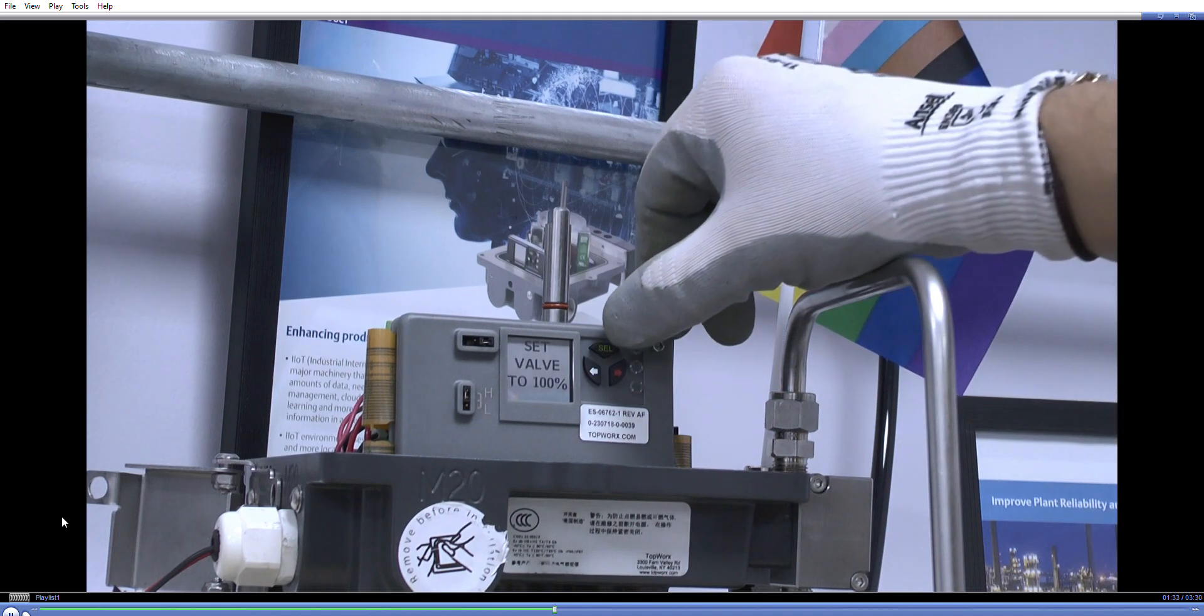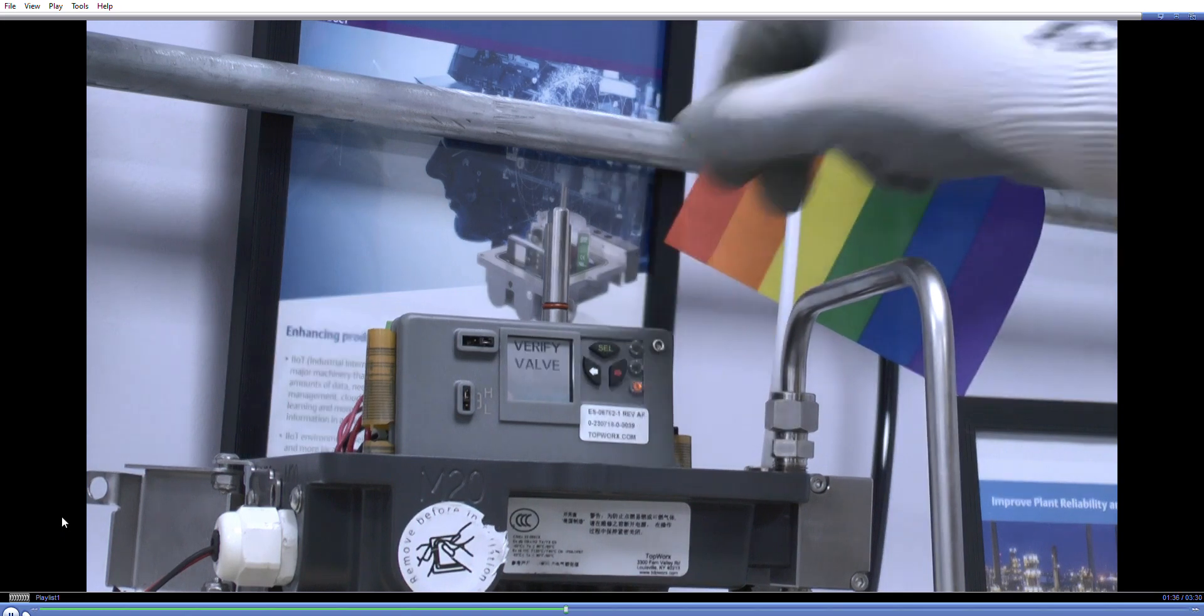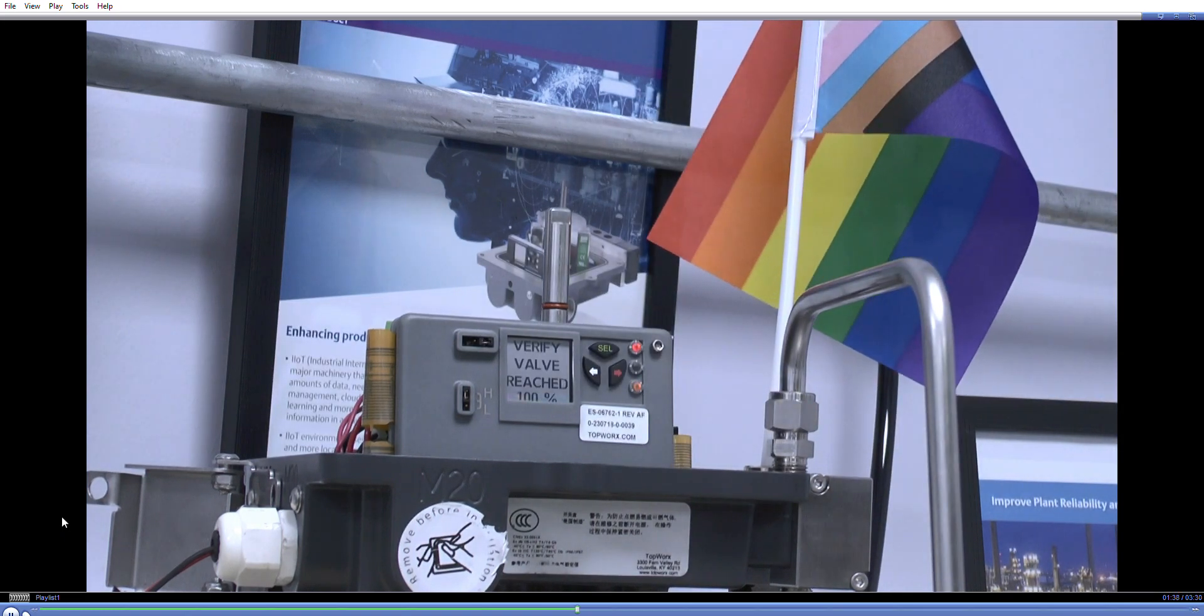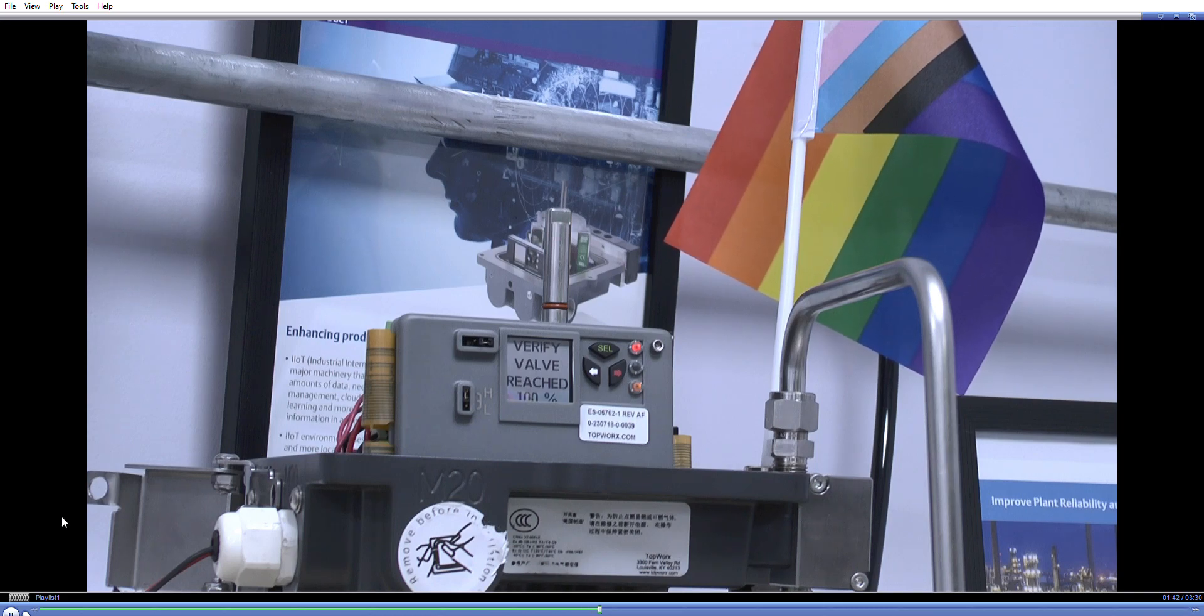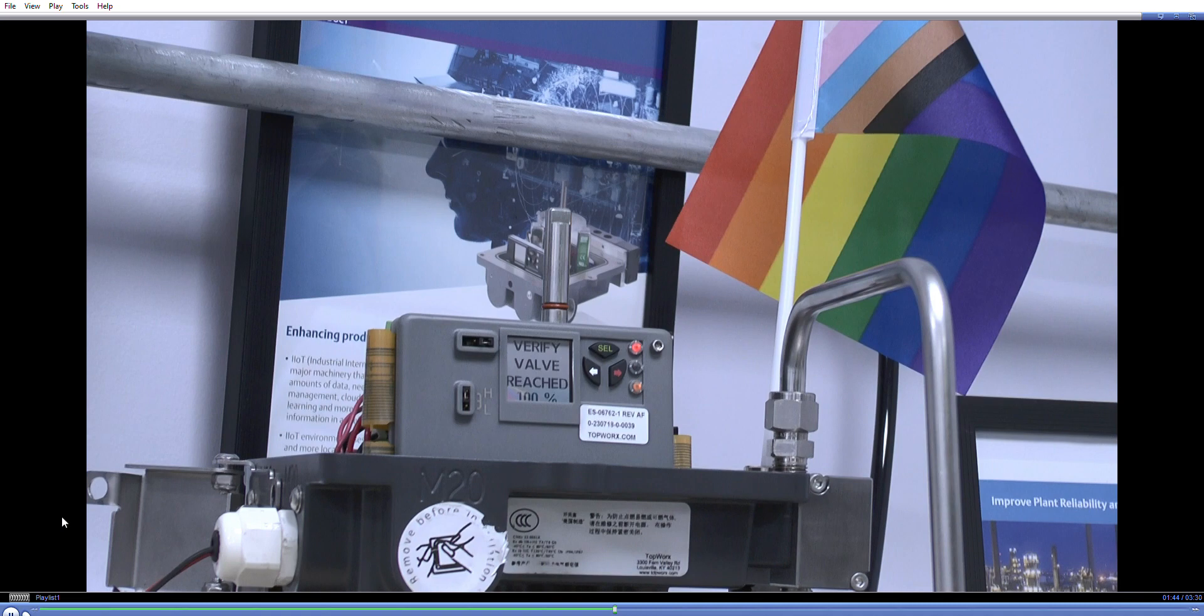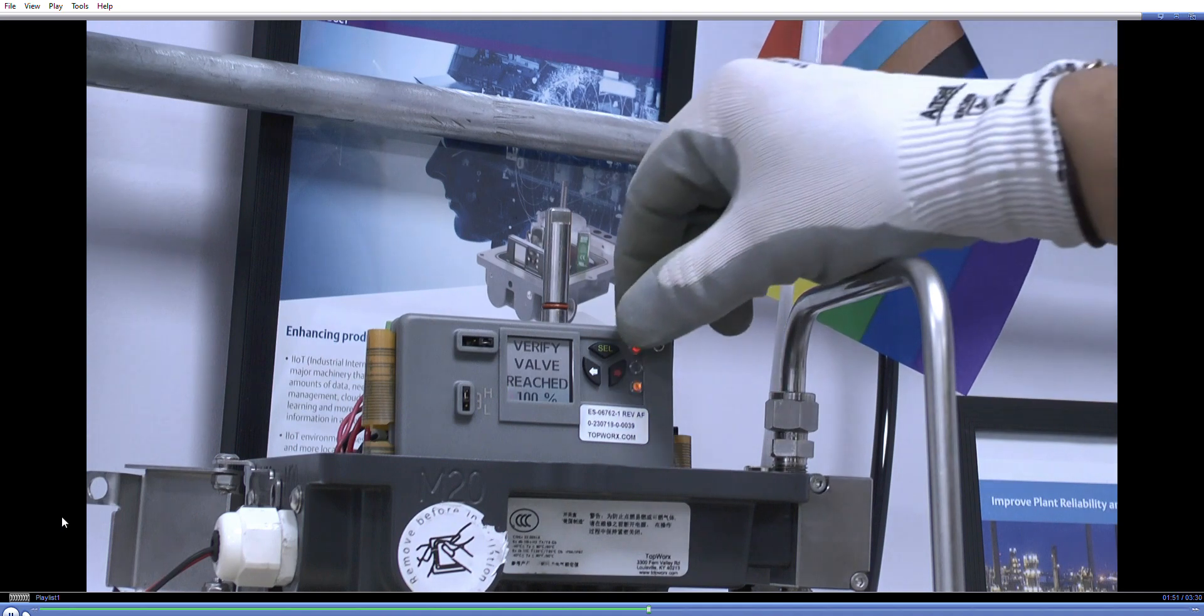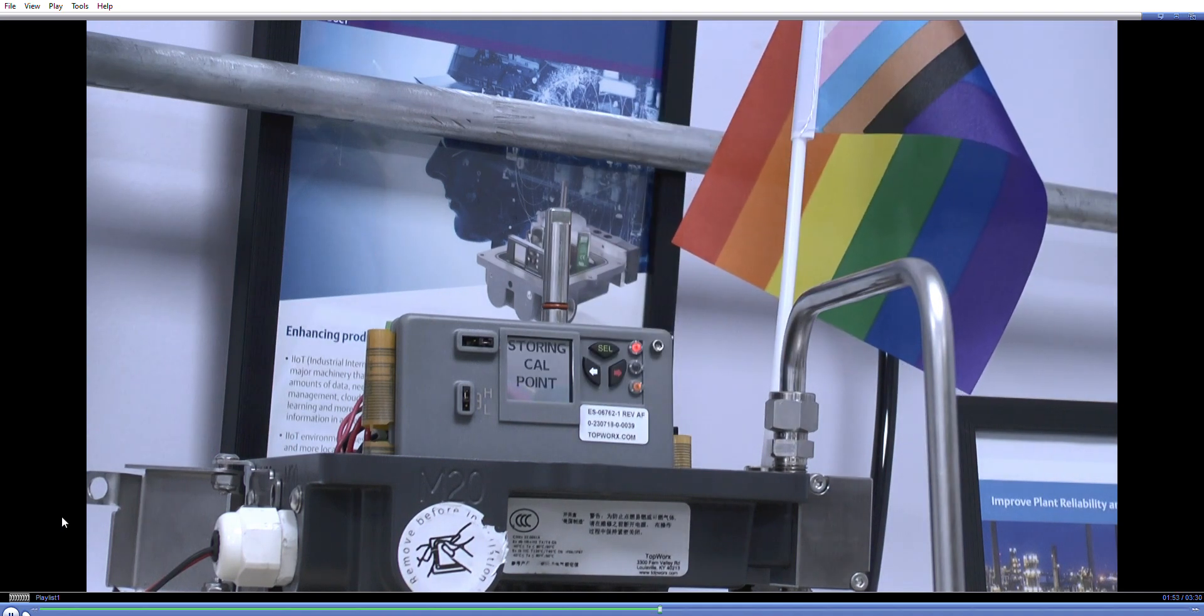Now we'll set the valve to 100% again, the valve will go through the cycle and set it to 100%. And again we just need a little bit of time then to register that position. And select, storing calibration point.